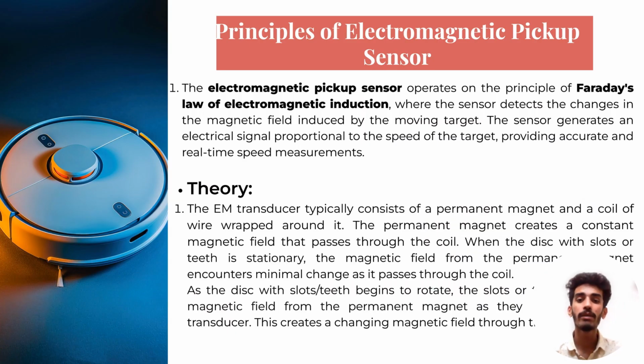Now let's talk about the principles of the electromagnetic pickup sensor. Basically, the electromagnetic pickup sensor operates on the principle of Faraday's law of electromagnetic induction, where the sensor detects the change in the magnetic field induced by the moving target. The sensor then generates an electric signal proportional to the speed of the target, providing accurate and real-time speed measurements.